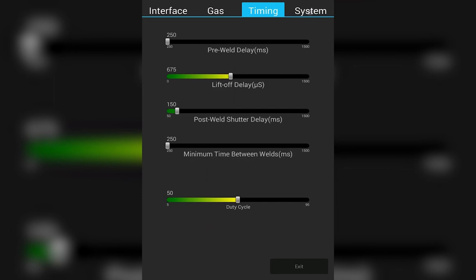The post weld shutter delay controls how long your optic shutter will stay closed after the weld is finished. The minimum time between welds allows you to control how fast a subsequent weld can be made. Finally, the duty cycle controls the agitation duty cycle, how frequently the energy is turned on or off when using agitation.